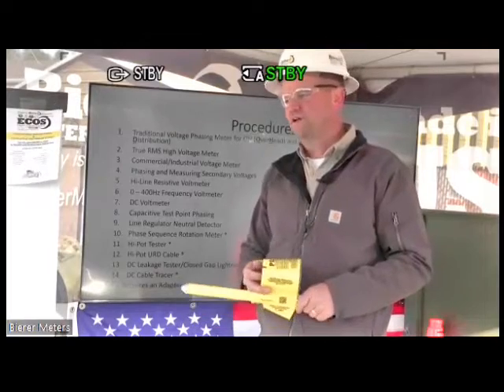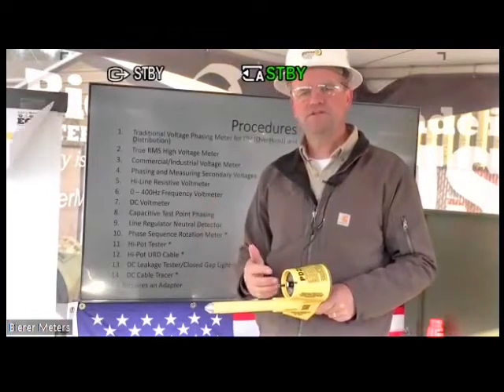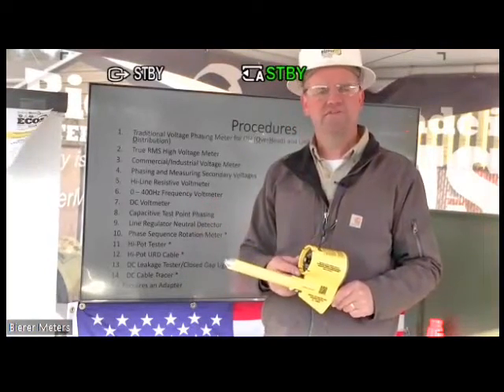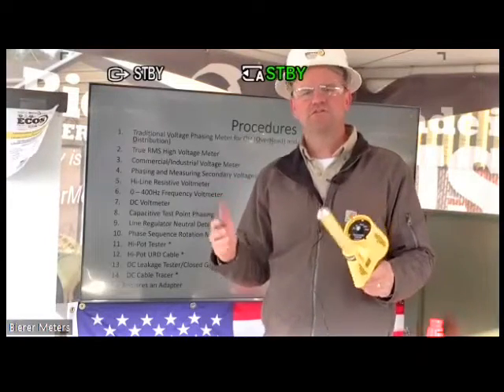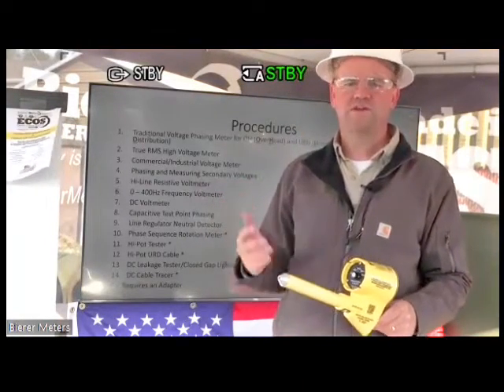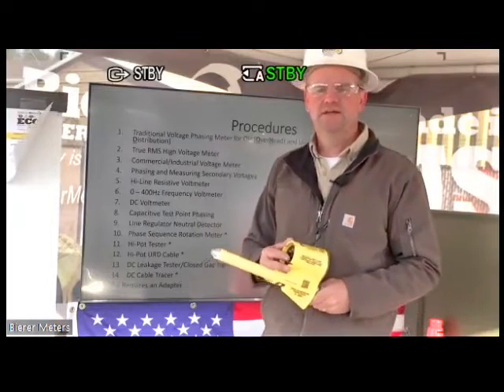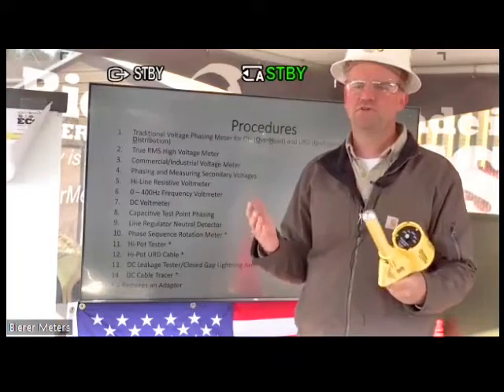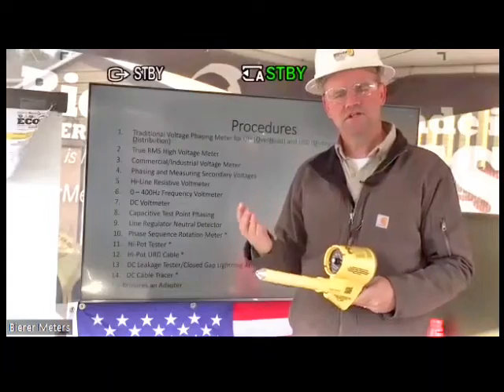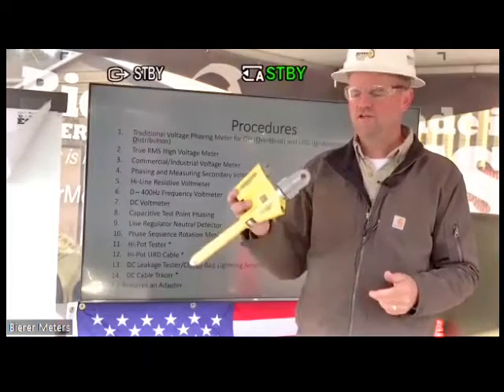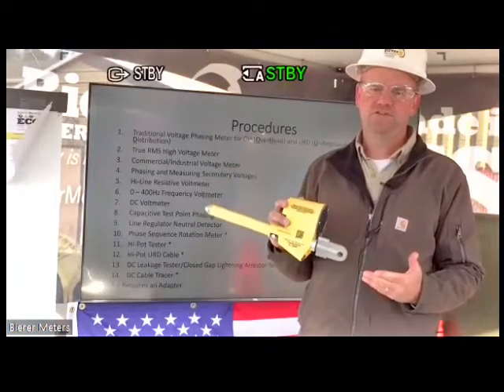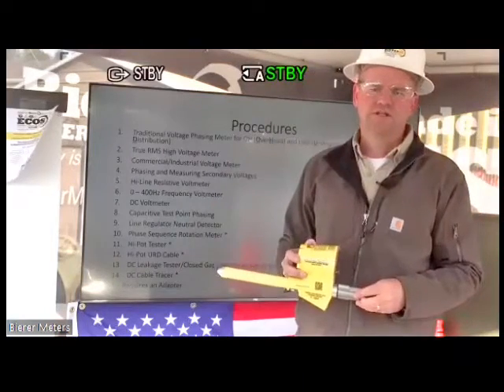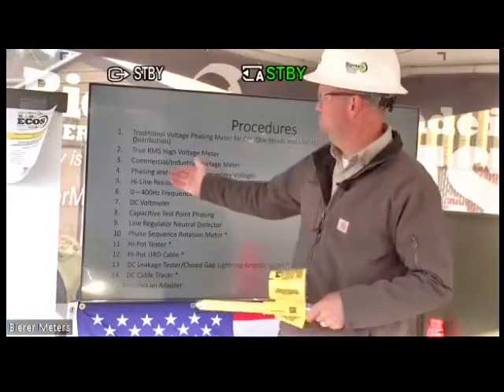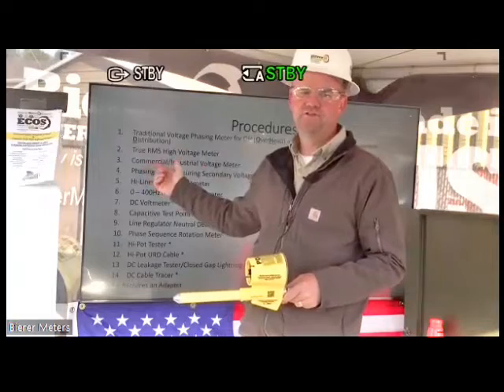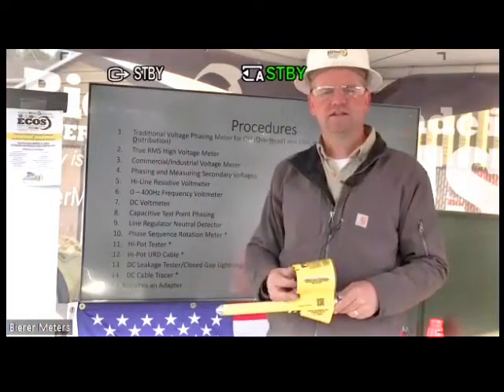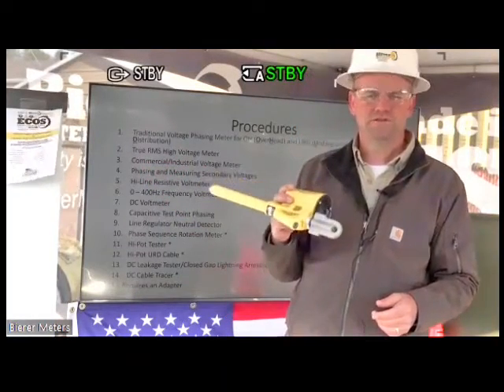meter. So in other words, just like the phasing meter that you may be using now that is not a PD25, you're using it to measure the difference of potential maybe across a switch, whatever the case may be. And you want to see a zero or near zero if you're in phase, some potential when you're out of phase. You can use a PD25 and a PD50 for that exact same reason. The difference is it's going to be a true RMS display. So if you notice on number 2 here on the list, this is a true RMS meter.